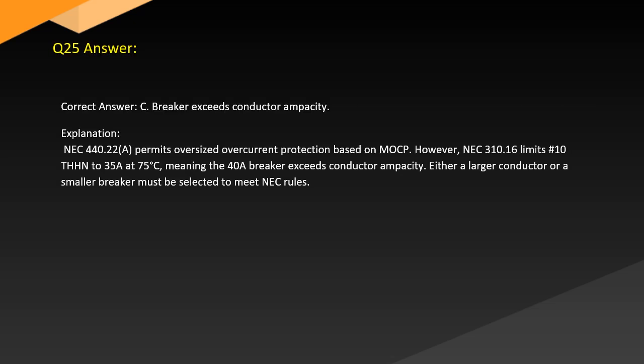Answer. Correct answer: C. Breaker exceeds conductor ampacity. Explanation. NEC 440.22(A) permits oversized overcurrent protection based on MOP. However, NEC 310.16 limits number 10 THHN to 35 amps at 75 degrees, meaning the 40-amp breaker exceeds conductor ampacity. Either a larger conductor or a smaller breaker must be selected to meet NEC rules.